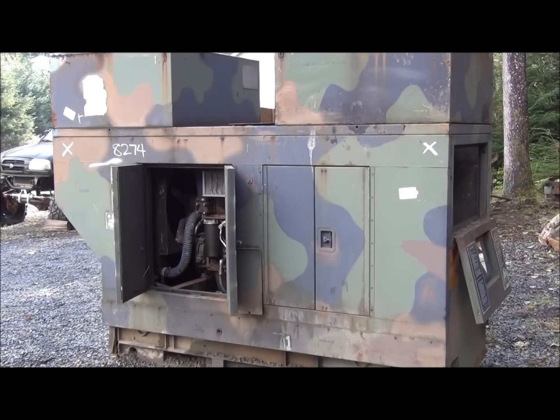Okay, I'm going to head on into the shop and spend a few minutes reading through the technical manuals and see what information I can dig up on the over voltage protection device. While I'm in there, I'm going to start the generator up and let it run so I can do the leak checks that I described earlier. I can bypass the overvolt protective device by placing the battle short switch in battle short. Having it there should ignore the over voltage trip. So we'll go ahead and fire it up and let it run for a few minutes, and I'll hopefully come back with some information on that protective device.